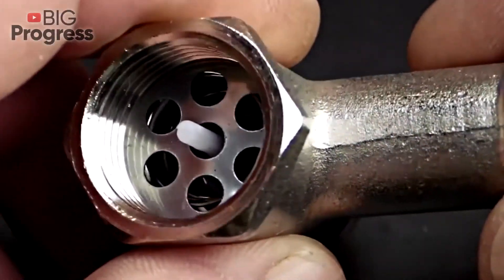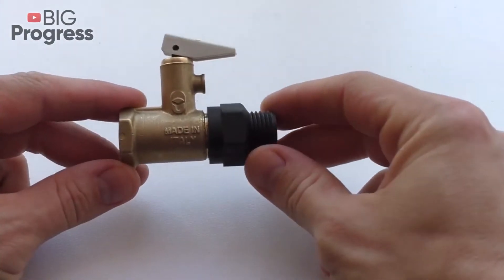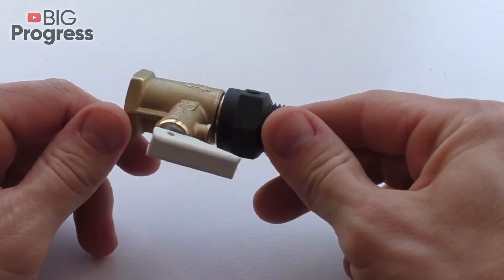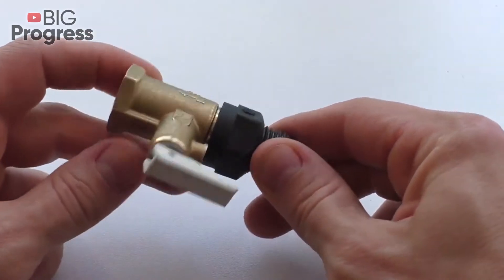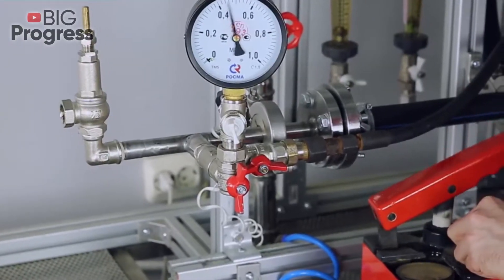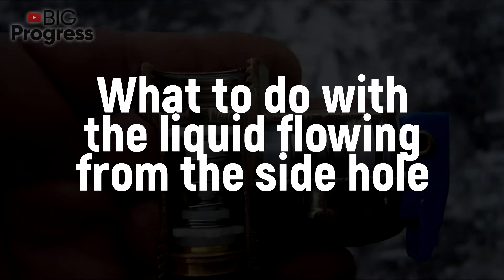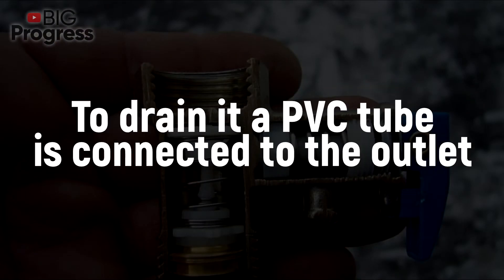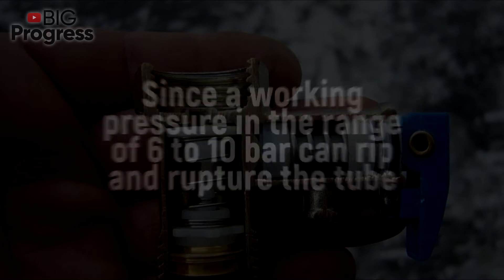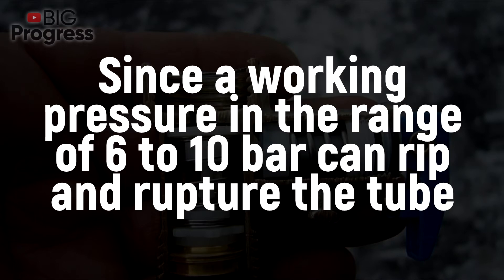Now that we know how this part works, it is easy to see why water often leaks near the output. This always happens when the water temperature increases and the pressure increases — it is a sign of normal operation. The question arises of what to do with the liquid flowing from the side hole. To drain it, a PVC tube is connected to the outlet. The tube must be reinforced and attached to the pipe with a clamp, since a working pressure in the range of 6 to 10 bars can rip and rupture the tube.